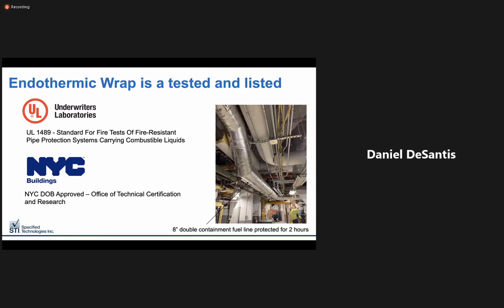So what exactly does third-party testing mean in the case of E-wrap for fuel oil line? We tested the product to the industry standard, UL 1489. This is a burn test conducted in UL's lab. Much like the test for electrical circuitry, there are strict pass-fail criteria. In order to achieve UL 1489, the average temperature rise along a protected fuel oil pipe may not exceed 250 degrees Fahrenheit above ambient temperature, and no one sensor may exceed 325 degrees above ambient to achieve a passing result.